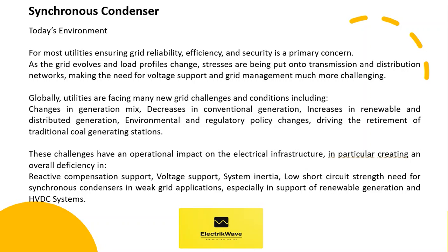Globally, utilities are facing many new grid challenges and conditions including: changes in generation mix, decreases in conventional generation, increases in renewable and distributed generation, environmental and regulatory policy changes driving the retirement of traditional coal-generating stations. These challenges have an operational impact on the electrical infrastructure, in particular creating an overall deficiency in reactive compensation support, voltage support, system inertia, and low short circuit strength — driving the need for synchronous condensers in weak grid applications, especially in support of renewable generation and HVDC systems.